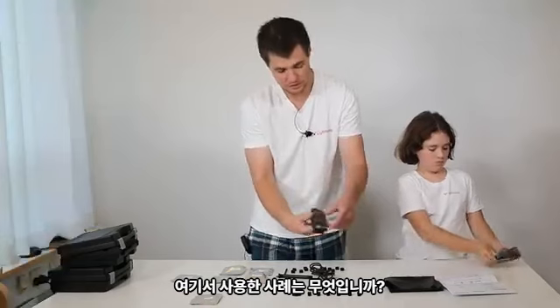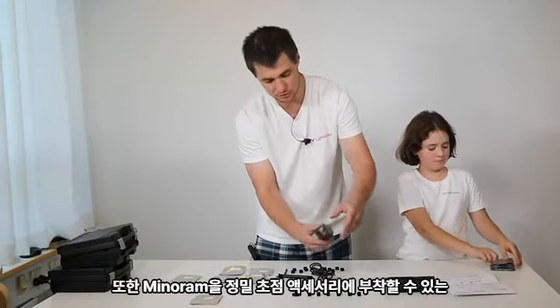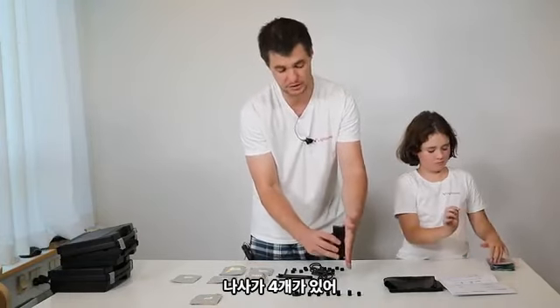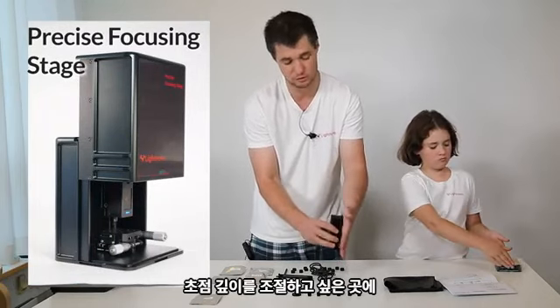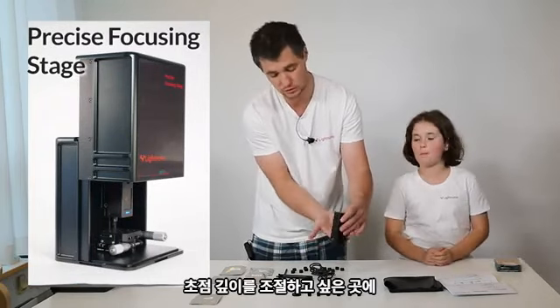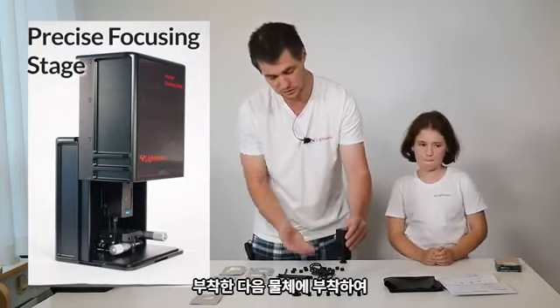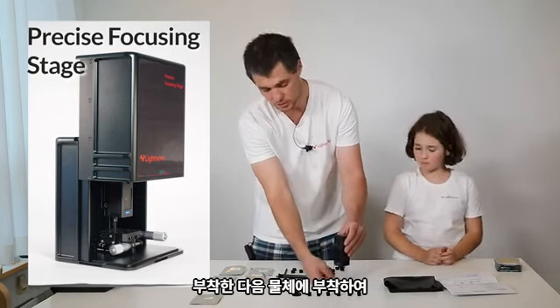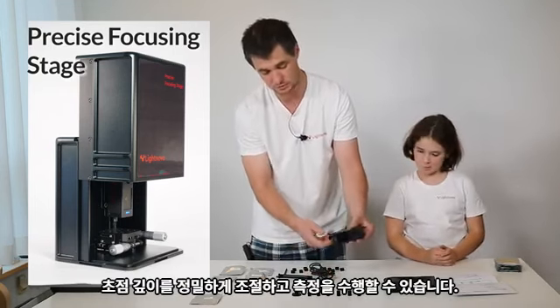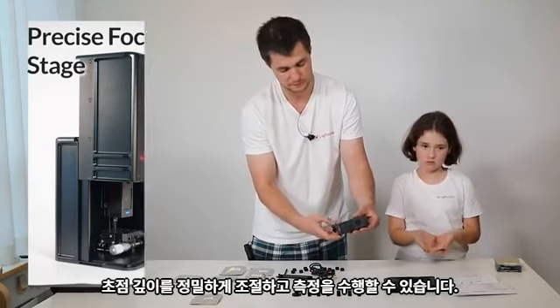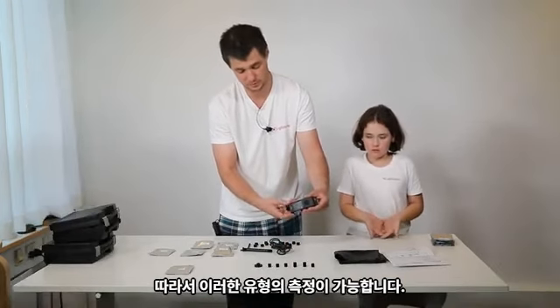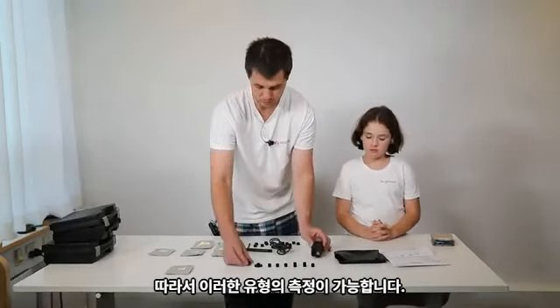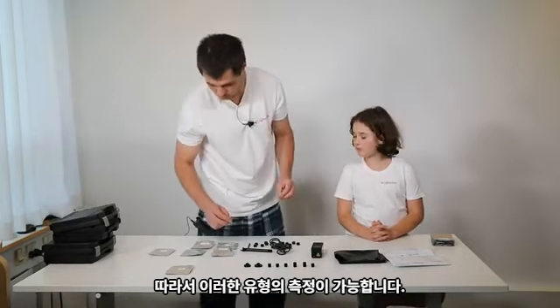What would be the use case? Here we have also 4 screws to attach mini Raman to our precise focusing accessory, or you can attach it to whatever you want to control the focusing depth, and then with the objective, you can precisely control the focus depth and do your measurements. So there is a possibility for those type of measurements.